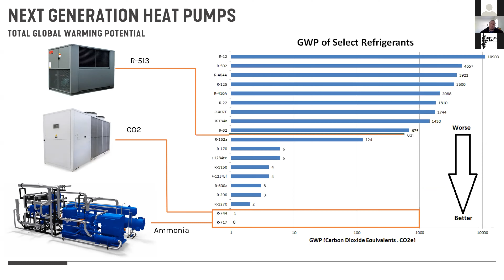So we've been working on an application of taking CO2 heat pumps, and this is a very crude diagram, of taking a high lift CO2 heat pump and pairing it with that low entropy design system that I talked about earlier, where instead of delivering 180-degree water to the building, we get down to, say, 120. If I can deliver 120-degree water, I can certainly get a 30-degree delta T or more on the hot water loop. But the key is to not use a heat exchanger.